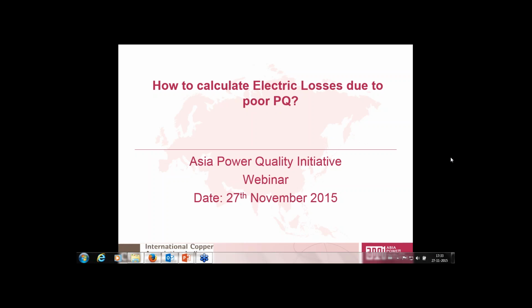The unbalanced currents are measured obviously separately. It's relatively straightforward to measure the currents. The overall problem, I guess, is then measuring the effects of those in terms of system efficiency, and that's why we look at the loss analysis that we do and the way that we calculate either using IEEE 1459 or using our unified power method. Thank you, Frank.